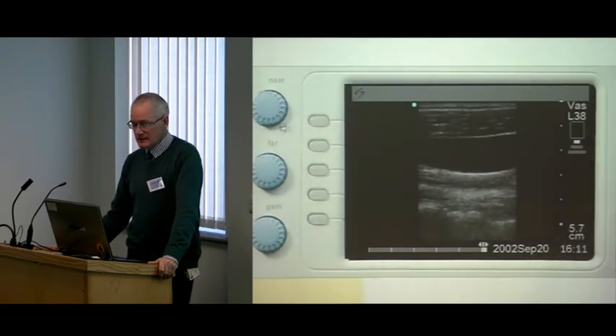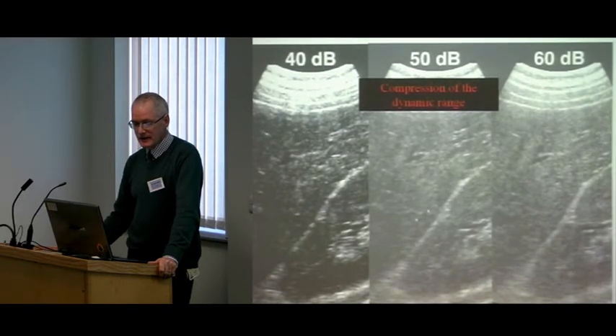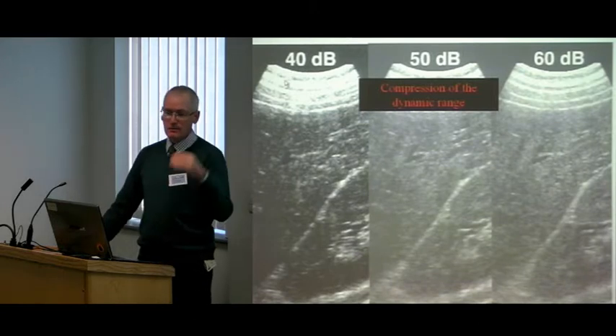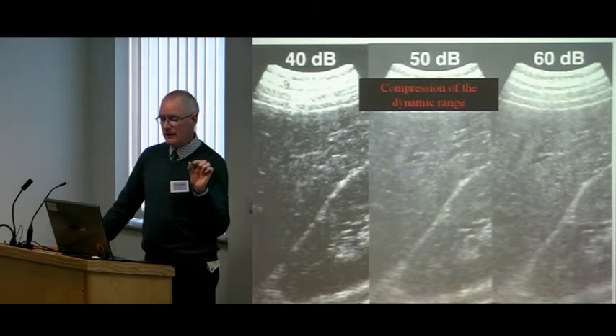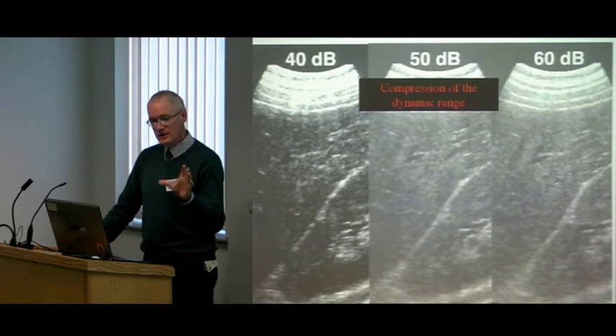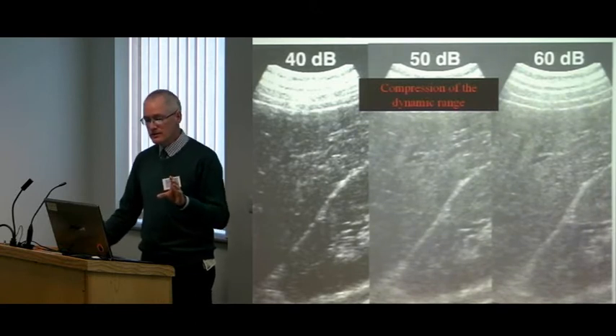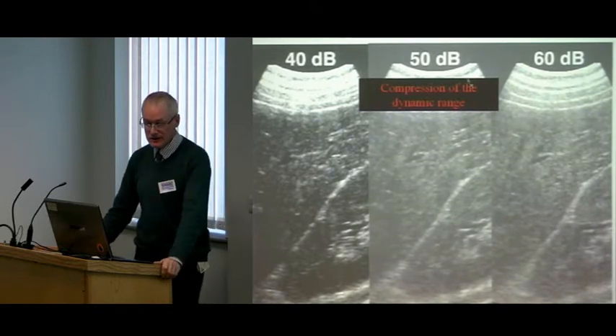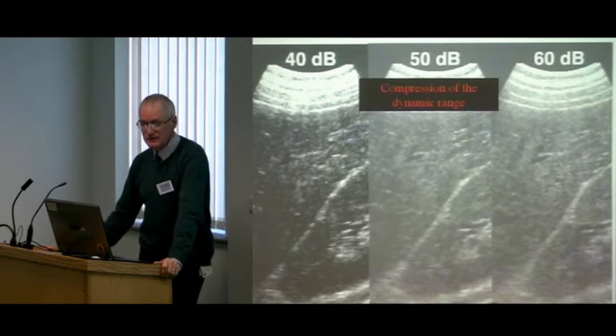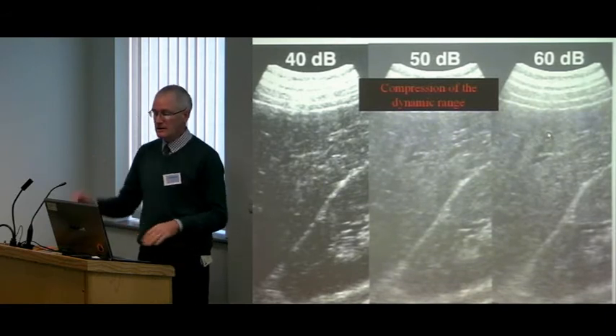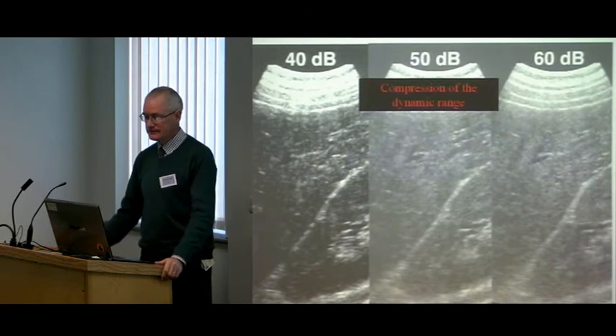So we've looked at that image before, we know a little bit about that. This is the effect of increasing the black and whiteness of the image, the dynamic range. By having a narrow dynamic range, the grayscale is very narrow, and therefore it's very black and white. So the compression of the dynamic range will produce a very black and white image, and will give you good edge detail at the sides of structures, but it doesn't give you very good internal detail of the parenchyma of the structure you're looking at, which occurs when you widen the dynamic range and make it more of a grayscale.